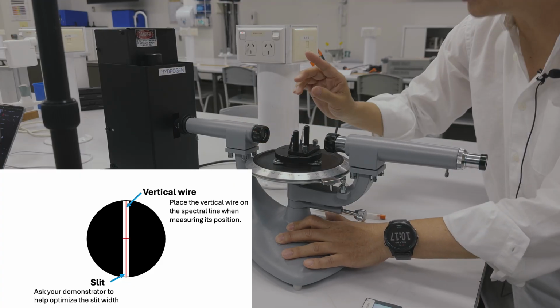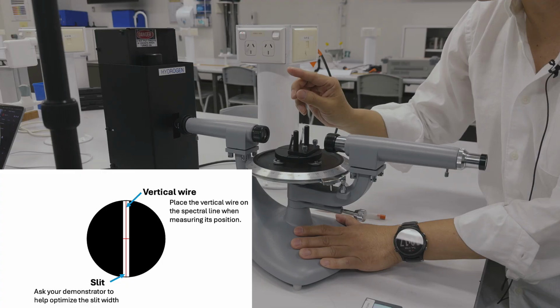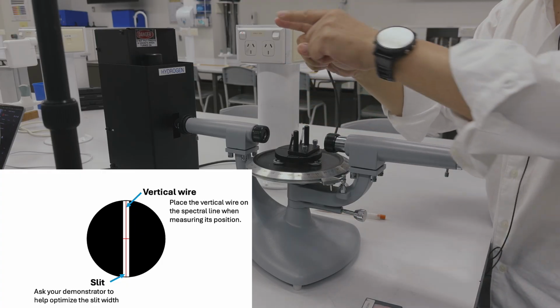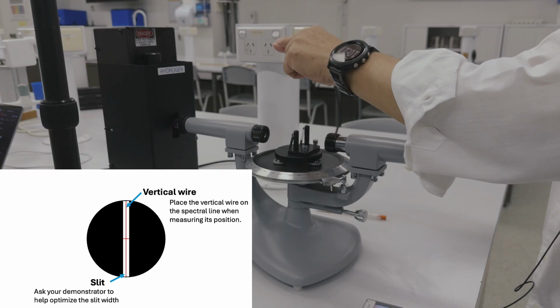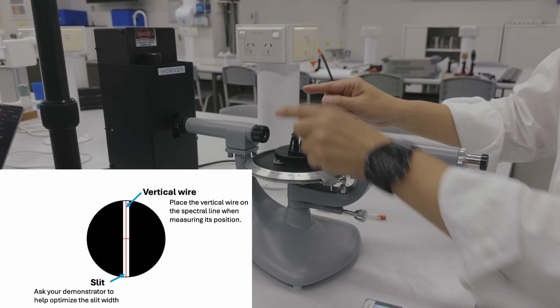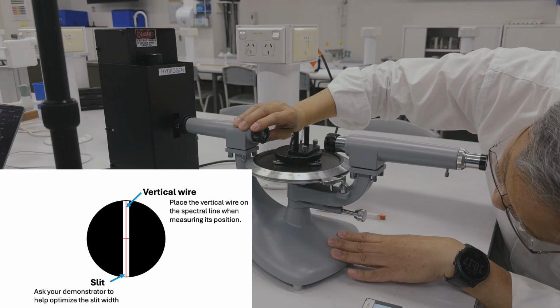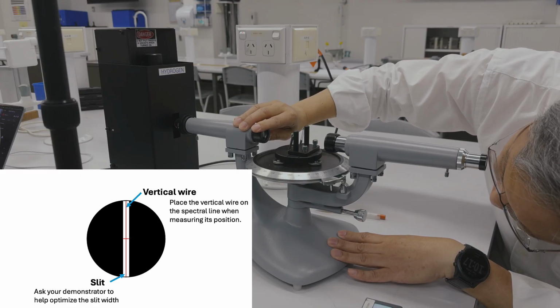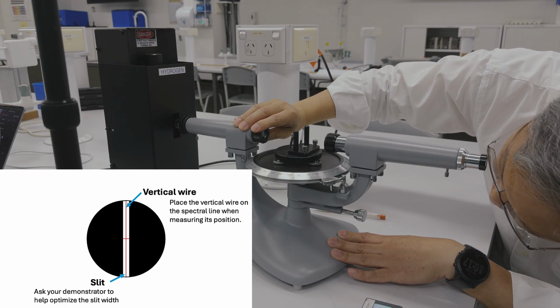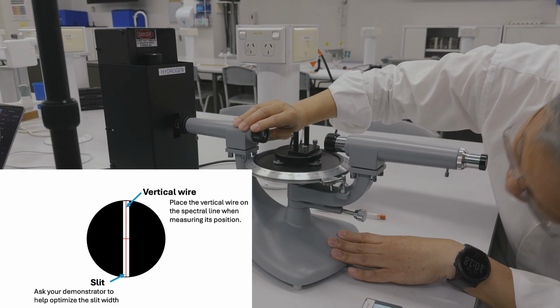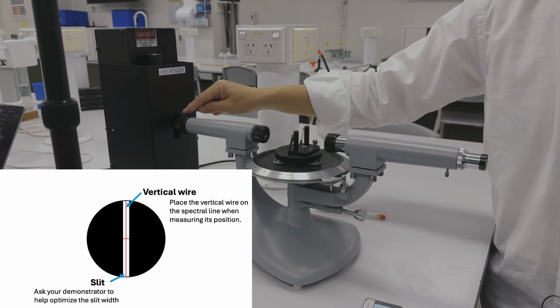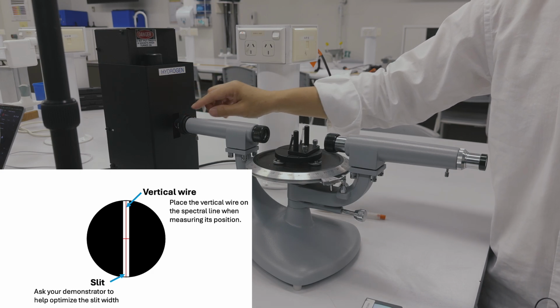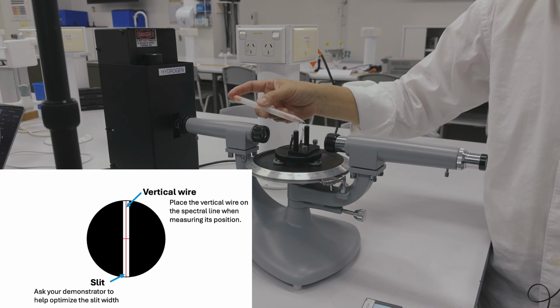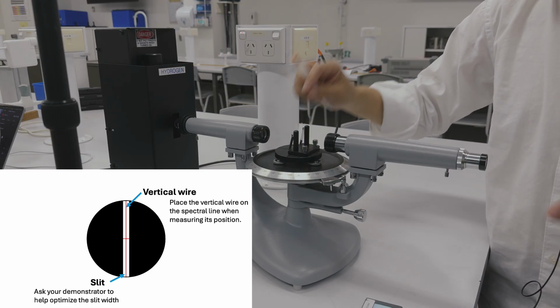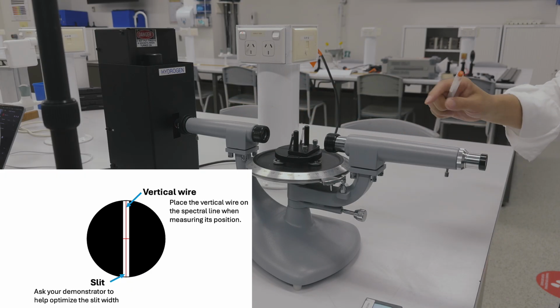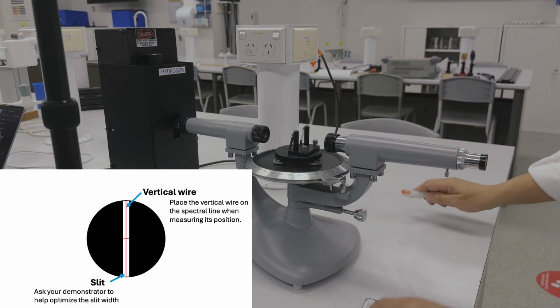Now, when I say clear, you are looking at the edge of the gauge. If this is the edge of the gauge you see, you want to make the edge in focus. So you rotate this one and you can see a little bit of dust sometimes, very close at the edge. Once the edge of the gauge or the slit is in focus, what does it mean? It means the light in this path is parallel. So now the optics is optimized.